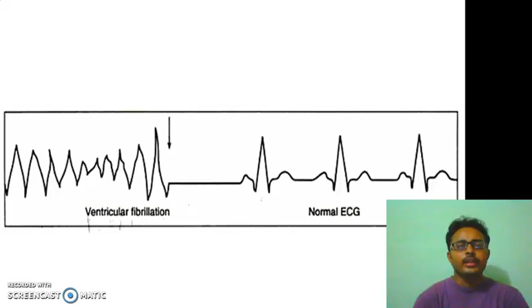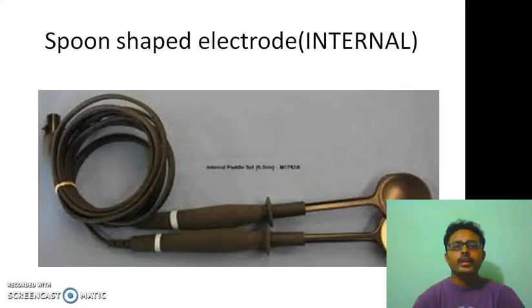The internal defibrillator is used when the chest is open, and the DC defibrillator can work under a voltage of 50 volts to 1000 volts, with a contact impedance of 50 ohms and 1 to 20 amps. For that, the heart requires 15 to 50 joules, and the shock duration is 2.5 to 5 milliseconds. These are the types of internal defibrillator. It uses a spoon-shaped electrode. And the external defibrillator uses a paddle-shaped electrode.